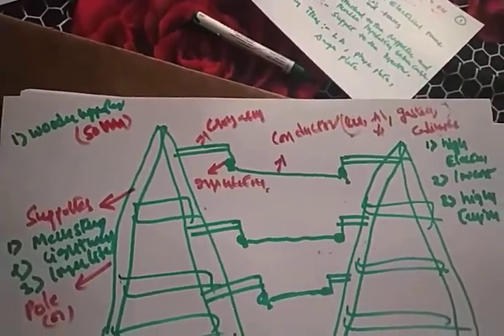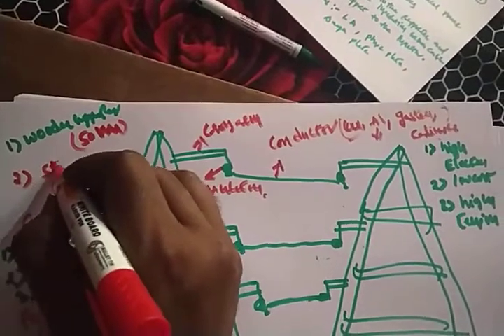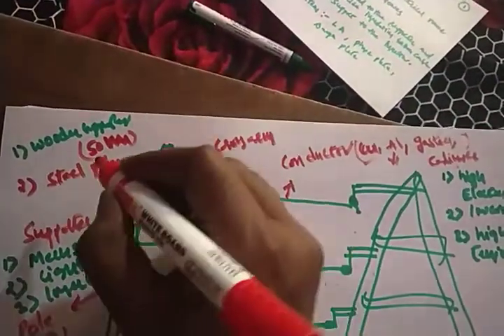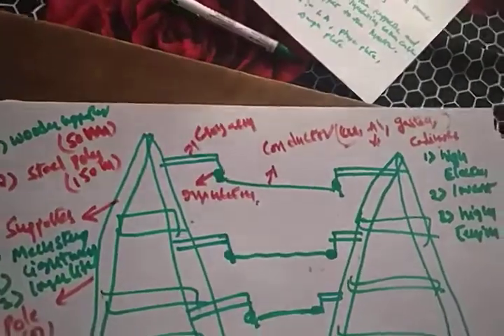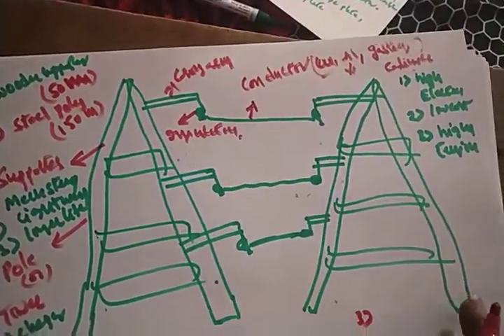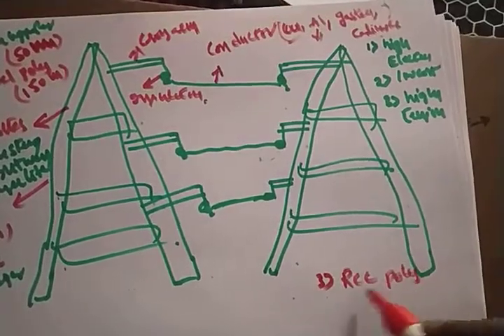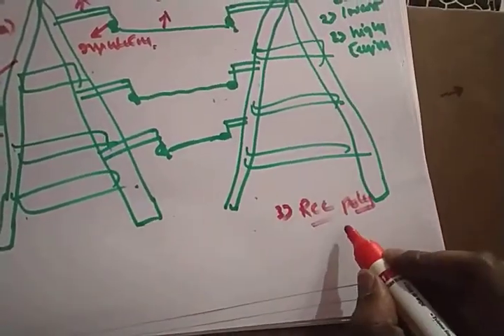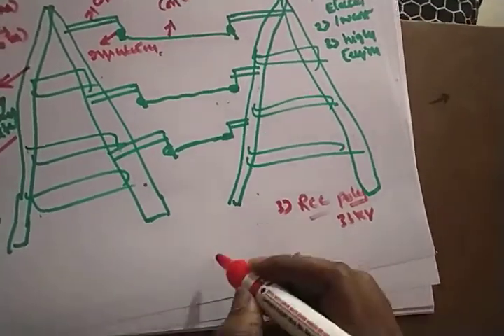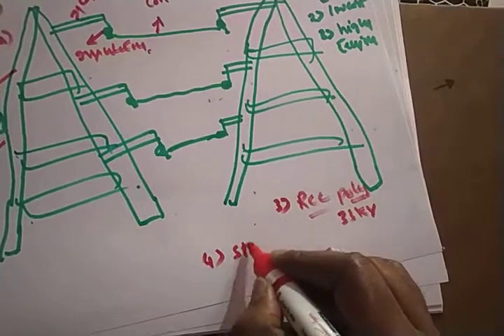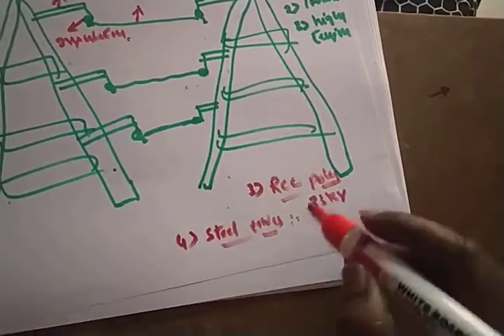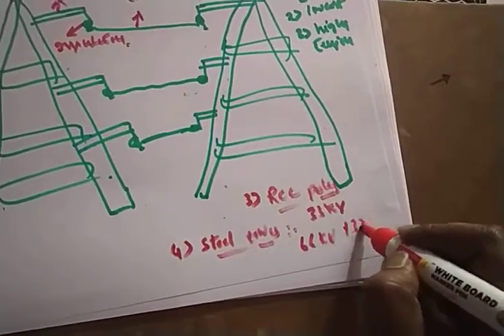After wooden supporters, steel poles were used — they can be used for up to 150 meters in length. Then there are RCC poles — reinforced concrete poles. Nowadays we use concrete poles for 33 kV transmission systems. For higher voltages like 66 kV and 132 kV transmission systems, we use steel towers.